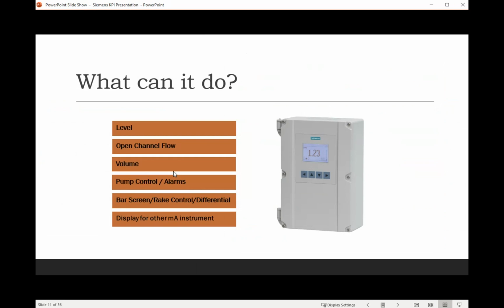Then a lot of people also forget that the Hydroranger can also take in a milliamp input. So for example, if you have a lift station and the ultrasonic sensor's not giving you what you need, not performing correctly, you could possibly run a submersible pressure transducer or a radar transmitter into the Hydroranger 200 into a milliamp input and use that as your control. You have the ability to have your relays, your display, and everything on there using the Hydroranger. You would need a little power supply there for it, but it's possible.